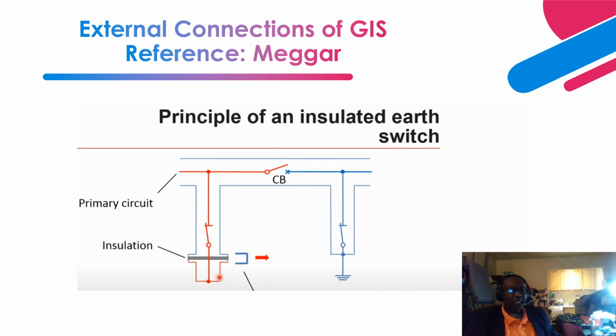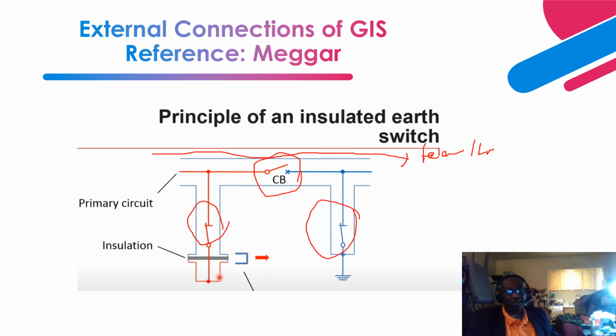Okay, so if you take a look at a line side, let's take this one as a feeder. Some people call it a line side. So you have a circuit breaker, then you have a disconnect switch here and a disconnect switch here. This disconnect switch has insulation, and on this side is your shorting block. Remember, it is shorted and taken to ground. Then this one also can be connected to ground.